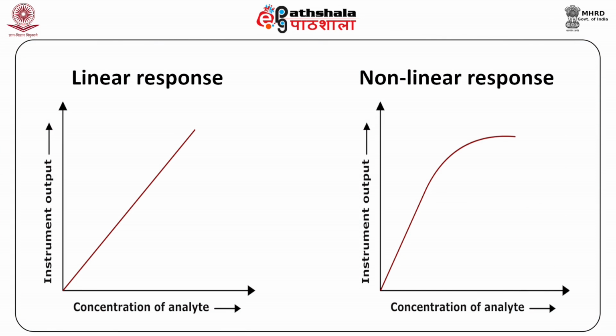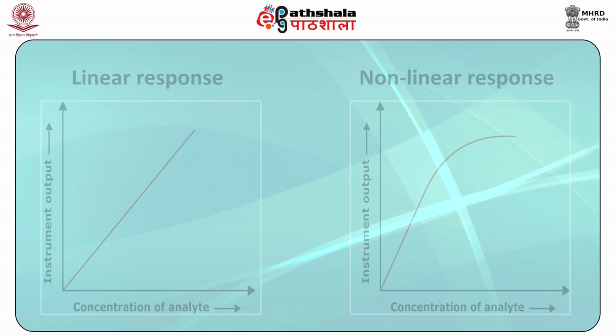It is usually desirable to maximize the sensitivity value unless one wishes to extend the instrument's range of response without diluting the sample. Figure 1 shows a linear response, that is constant sensitivity, over the entire range of measured concentrations. The non-linear response in figure 2 indicates a constantly changing value for sensitivity as a function of concentration. Measurements of substance C become less sensitive with increasing concentration. Sensitivity may also be expressed as the concentration of analyte required to cause a given instrument response.